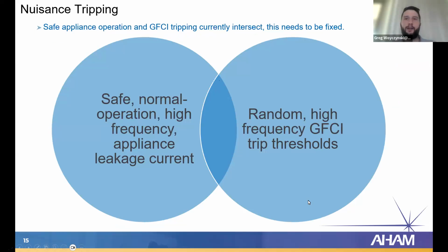So, summary here: why is nuisance tripping happening? There is an intersection of safe, normal operation, high frequency appliance leakage currents, and these random high frequency GFCI trip thresholds. Those 2 things should not be intersected. If the appliance is safe, the GFCI should not be tripping.